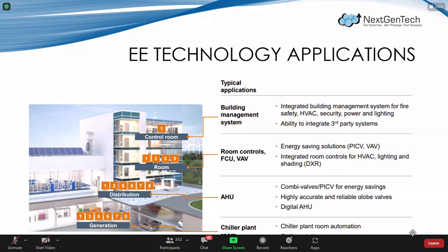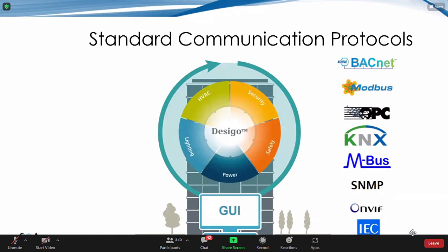In the energy savings of a building, one of the key technologies that must really be scrutinized, changed, upgraded, or modified is the chiller. That's the most important in generation, about 50 to 70 percent as Sir Carlos pointed out. A lot of energy savings can be realized from having efficient controls in the chiller plant rooms.